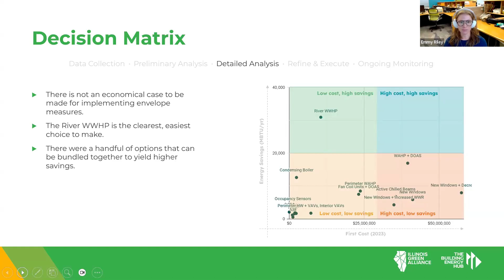We ended up doing four bundles of measures. The first one had what we'd consider zero incremental cost—measures the building would have to do anyway. The second, more expensive bundle but with the biggest incremental efficiency gain, was what we called the balanced approach. It included things like that water-to-water heat pump for the river that I love so much. We also found that on-site solar, even with not a very big footprint on the roof, had a pretty good economic analysis associated with it.